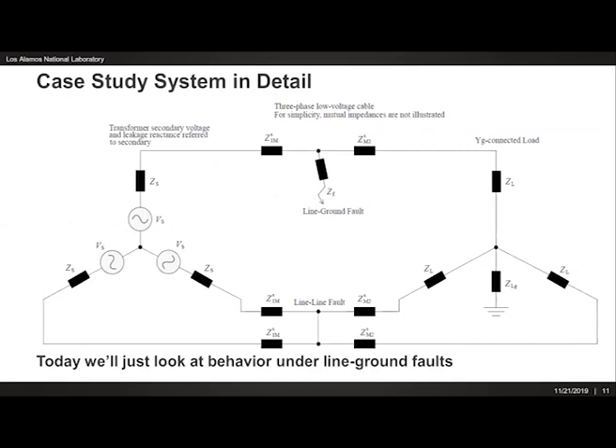When I break out the system one line into its individual conductors, we have a look at what the line to ground fault looks like. And what this results in is, neglecting the load, we're going to get a fault current along phase A, and phase B and phase C will be approximately zero current.